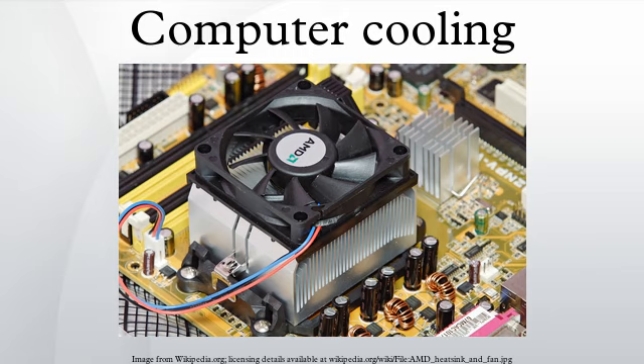Rack-mounted. Data centers typically contain many racks of thin, horizontally mounted 1U servers. Air is drawn in at the front of the rack and exhausted at the rear. Because data centers typically contain large numbers of computers and other power-dissipating devices, they risk equipment overheating. Extensive HVAC systems are used to prevent this. Often a raised floor is used so the area under the floor may be used as a large plenum for cooled air and power cabling.